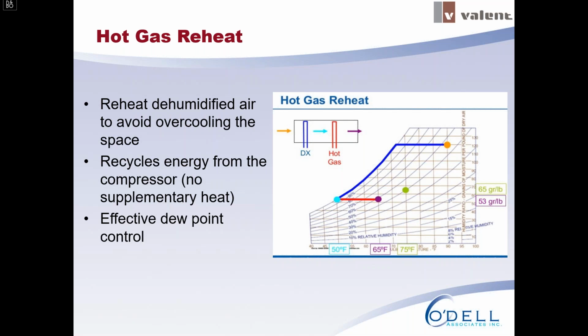So it's an efficient process, and in a lot of cases, when you're in dehumidification mode, it doesn't require any supplemental heat to get you back to your dry bulb set point. Now, I mentioned earlier that let's say you have a lab critical application, maybe you're at part load conditions and you don't have enough capacity for the hot gas reheat because your compressors aren't running as much, then you might need to do some extra reheat with, say, an electric heater or hot water coil. But when we're in dehumidification mode, typically the hot gas reheat coil is sufficient to heat that air back up to room neutral.